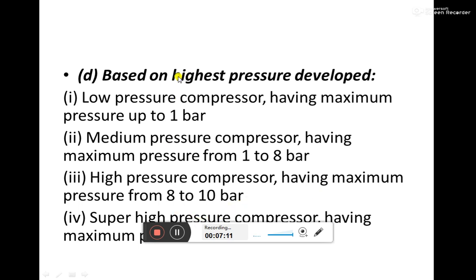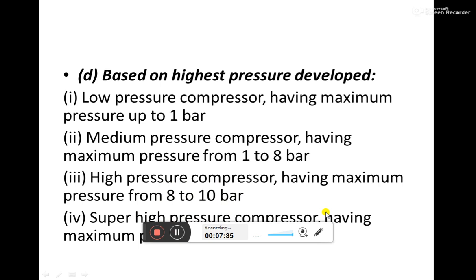Another classification is based on the highest pressure developed. A low pressure compressor has a maximum pressure up to 1 bar. A medium pressure compressor operates between 1 and 8 bar. A high pressure compressor has a delivery pressure in the range of 8 to 10 bar, and above that it is termed a super high pressure compressor.